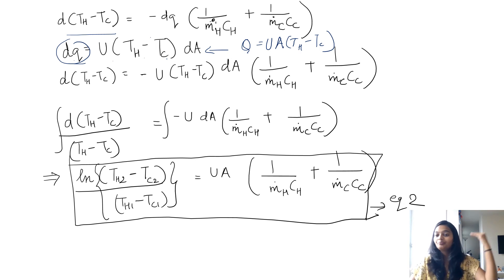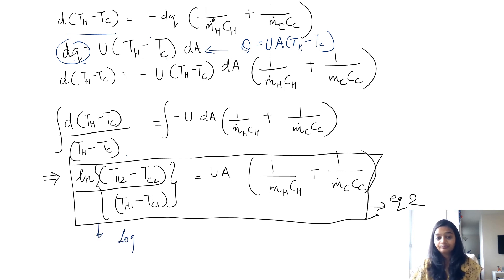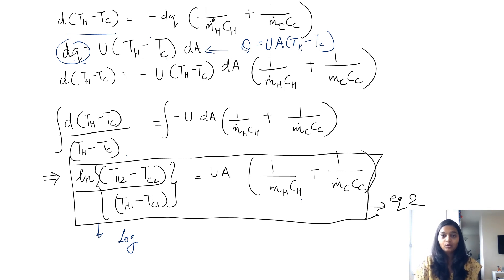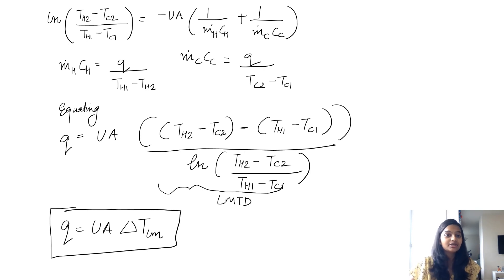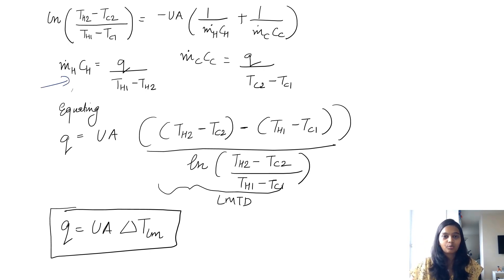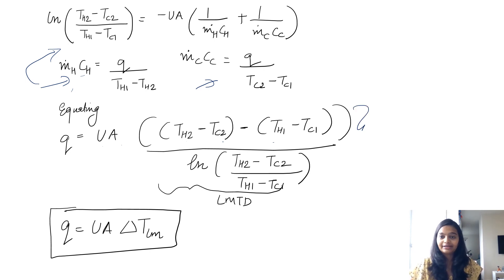Integrating on both sides, using the values at the two ends, we get the equation where the log term comes into play. The log of the temperature difference between the two ends equals UA times (1 over MH CH plus 1 over MC CC), representing both heat capacities. Replacing MH CH using the previous equation — which relates to the temperature difference between the two ends — and substituting both into this equation, we get Q equals UA times (TH1 minus TC1) minus (TH2 minus TC2), all over the natural log of those differences.